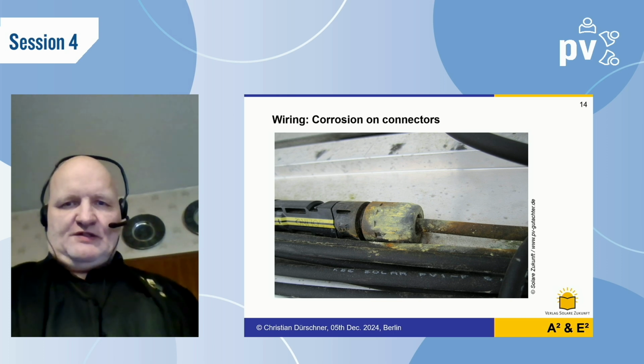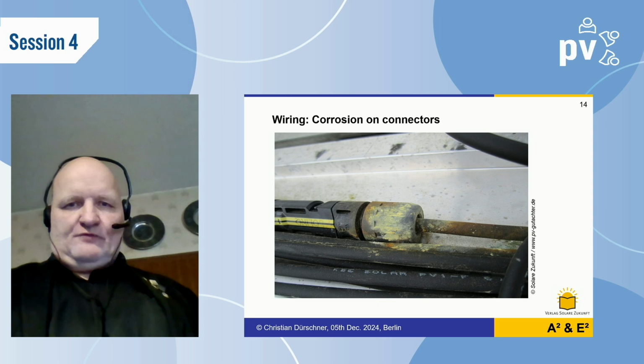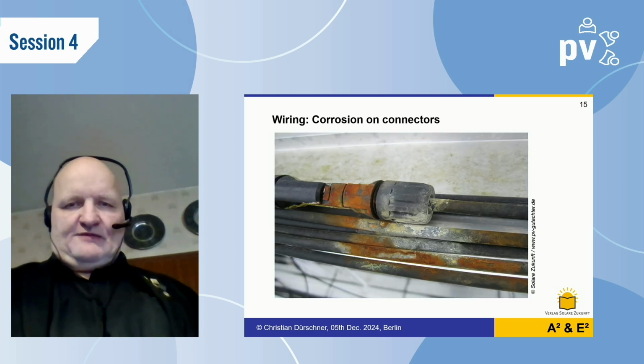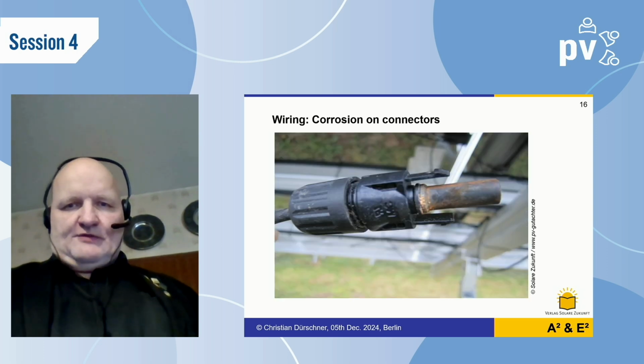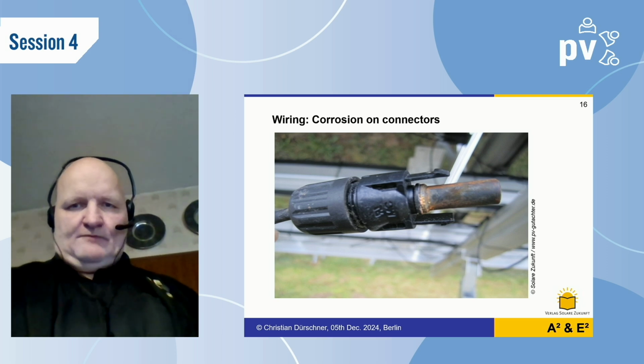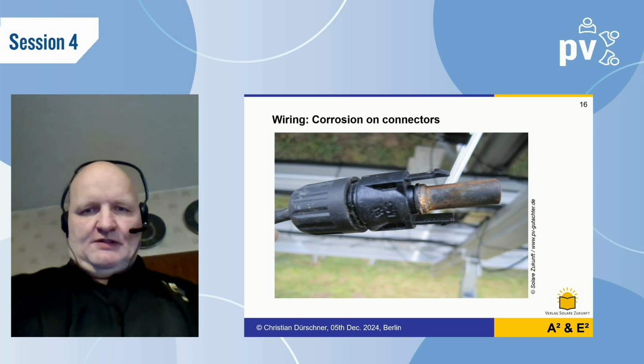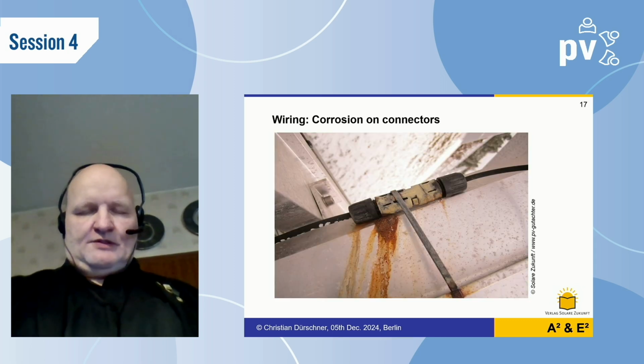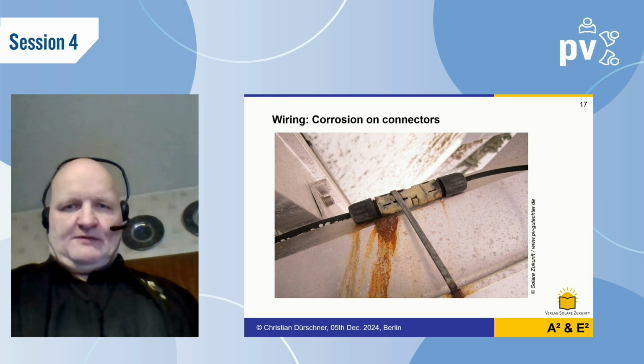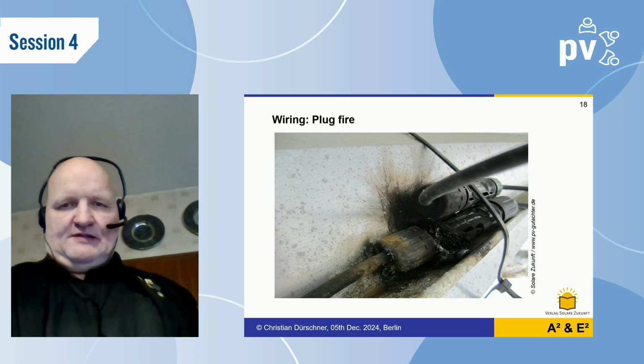You see here different manufacturers, female from one, male from another, and then it goes wrong. It shows corrosion. Also on the next one, corrosion. The third shows corrosion also inside, so it's not very tight and humidity or water can pour in and make the connection worse over time. We see it here again, and this leads at least to fire.